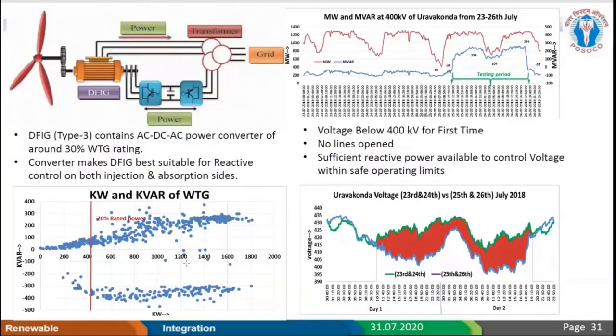Another important aspect we learned from that experience is that this doubly-fed induction generator, type 3, has an AC converter which can have 30% of the rating. If you see the individual profile, after 20% rated power, unlike solar, here night mode was not there. So if generation is there and it is above 20% of rated power, you see the bottom portion, absorption, is almost equal to the injection side. That means if there is injection in terms of megawatt, over 20% we have a good amount of MVAR absorption capability also.